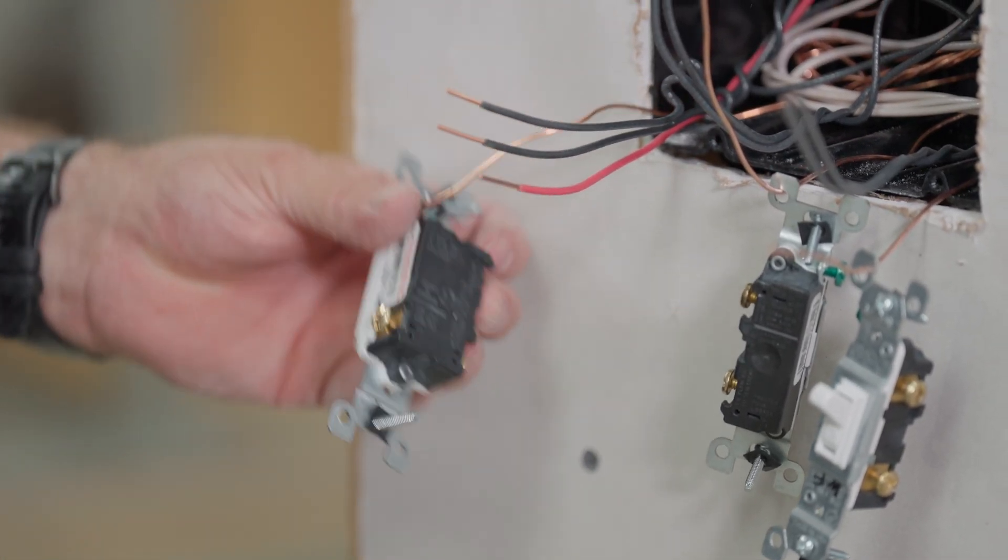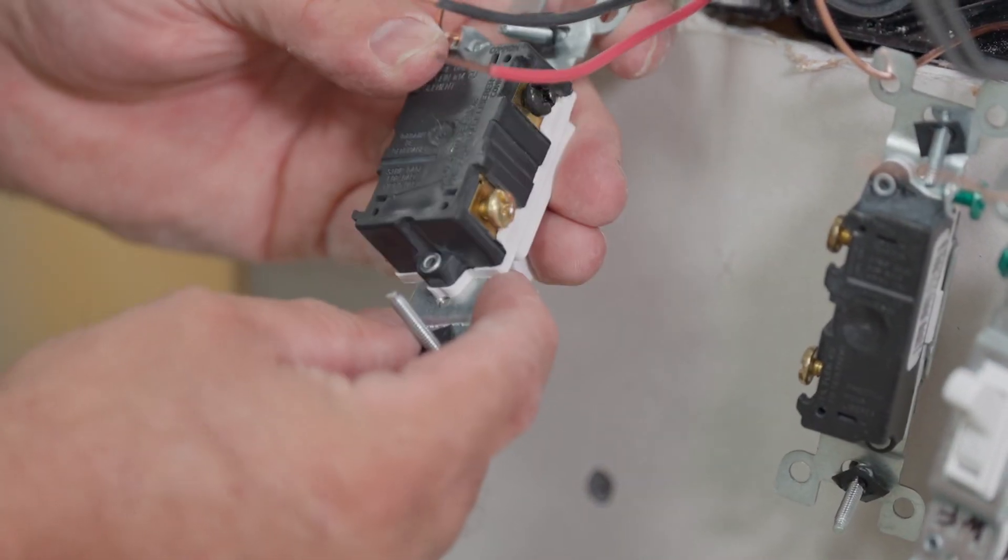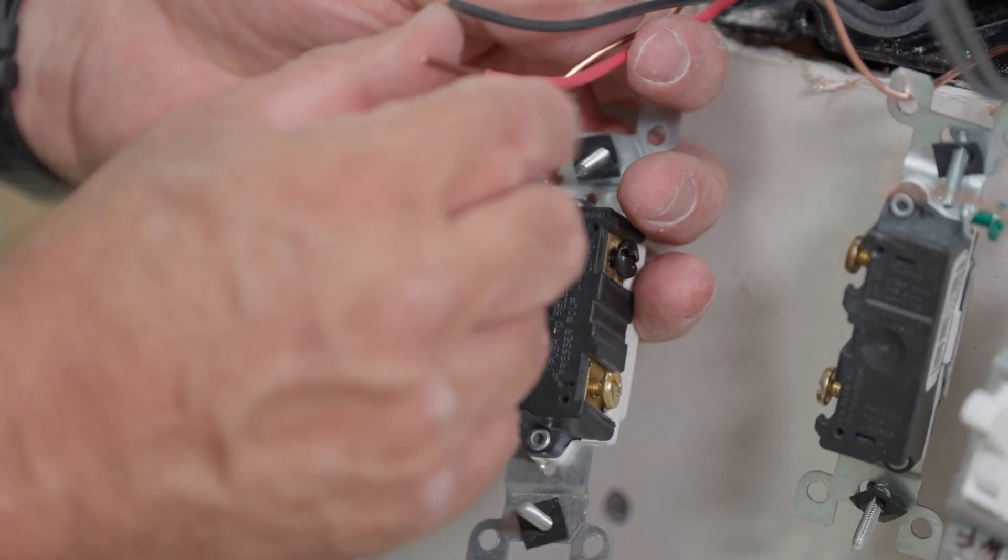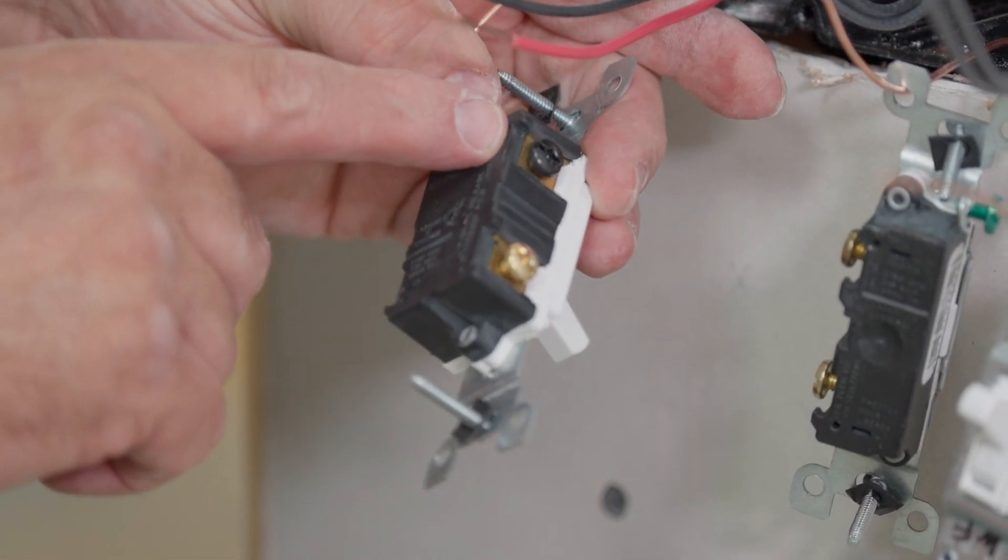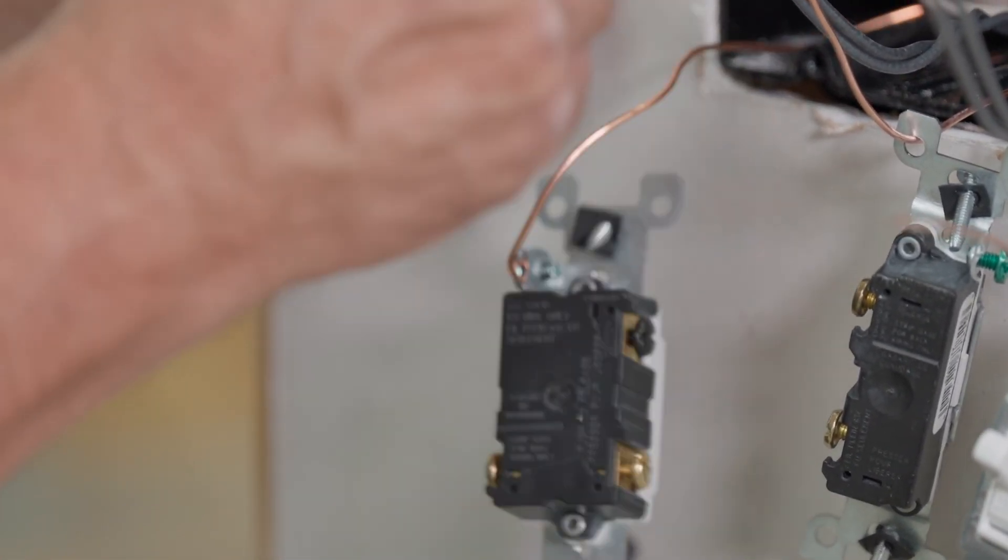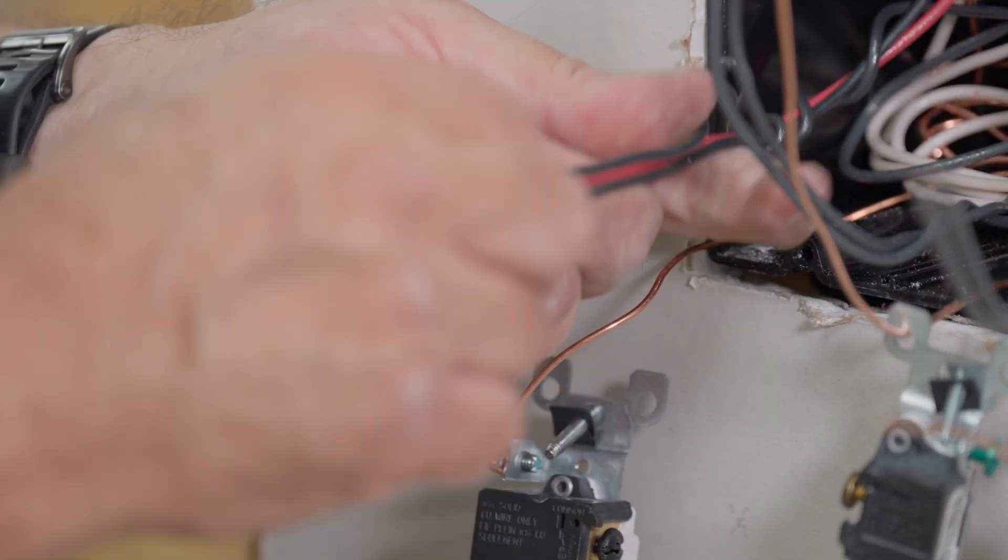Now this is a three-way switch. If you look at the back of this switch, you'll see two brass terminals. Those are for the travelers. And then there's the black common terminal. If you look at this, the makeup here, the travelers are here because this wire has been wrapped around and you can see that it's got a little extra twist. This is definitely the common wire.